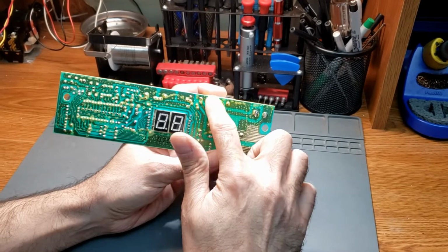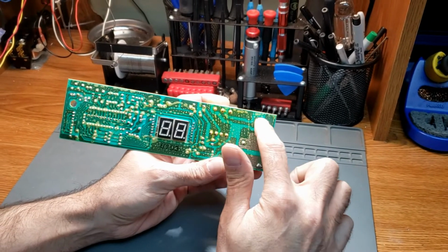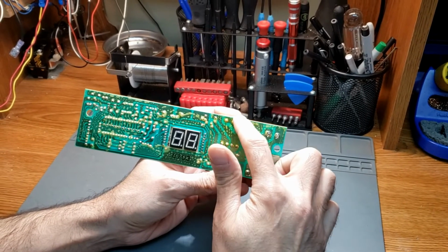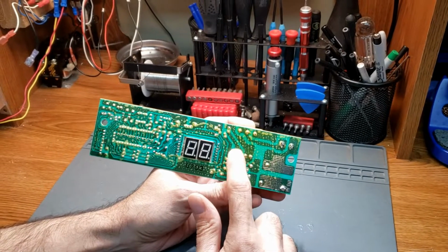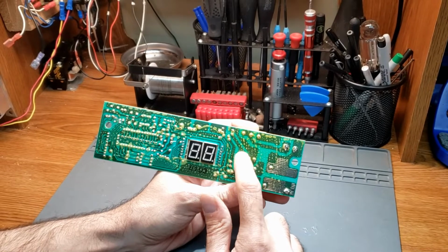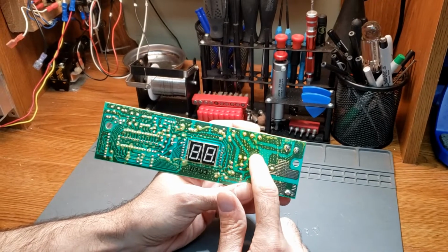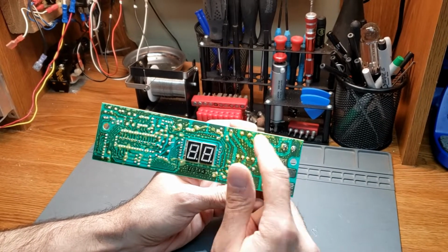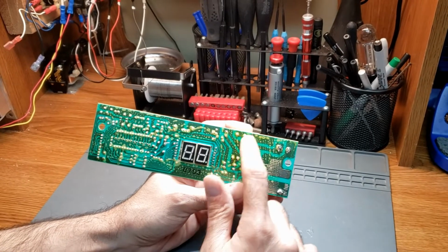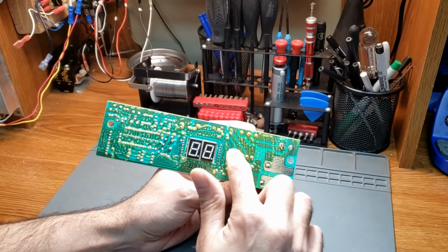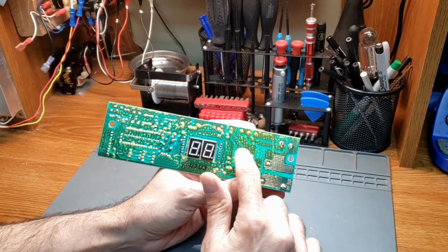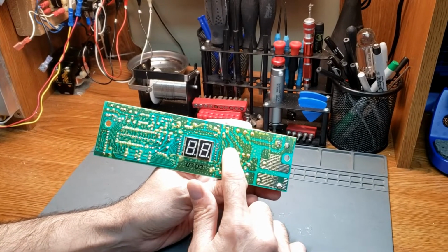Now I know that this transformer has a 120 volt primary. There's 120 volts set to come in here. And then here are the secondary terminals. This is where it should be putting out about 13 volts, but it's actually AC in this circuit. A lot of times your transformers will step it down from 120 volts to 12 volts DC, but I know that this is supposed to put out AC at a lower voltage.